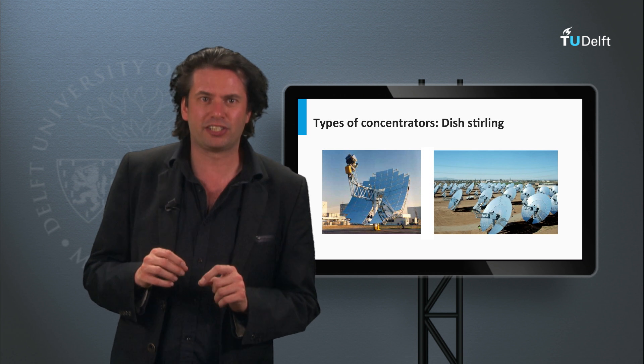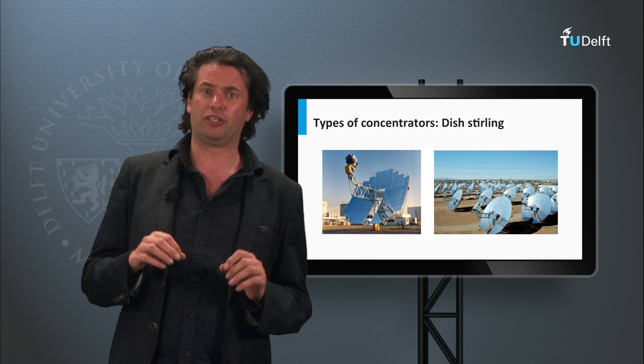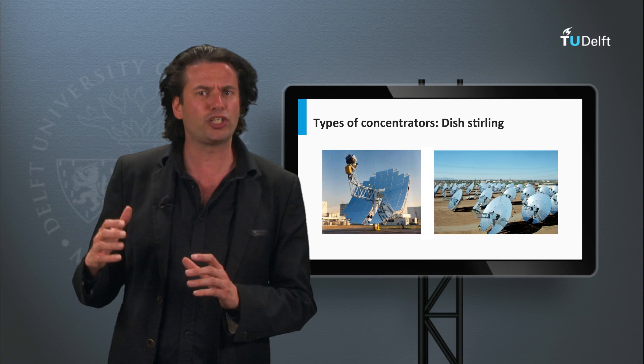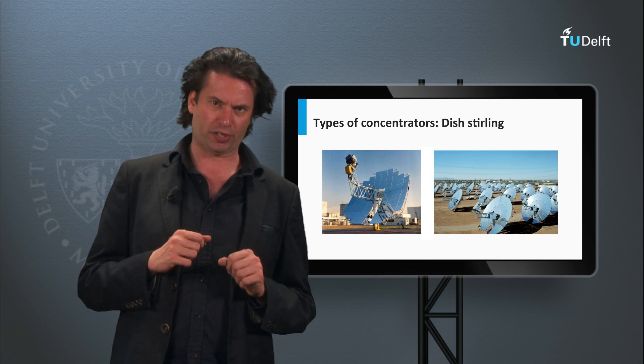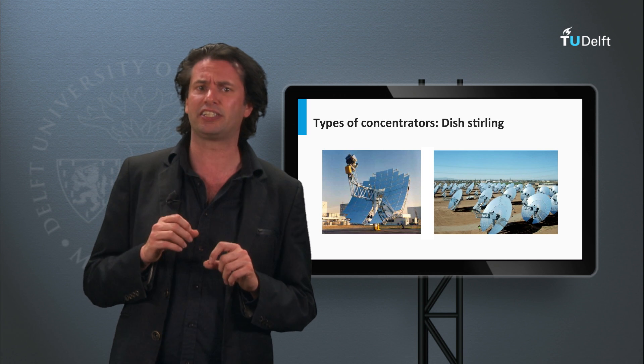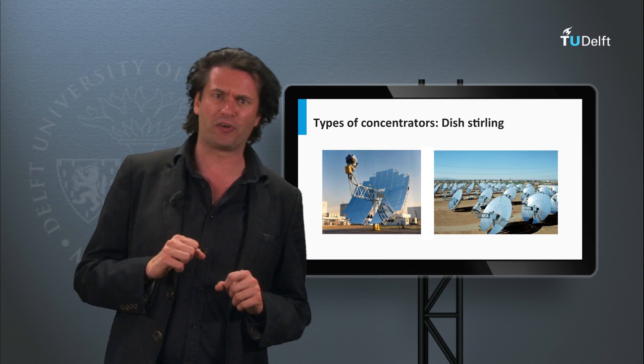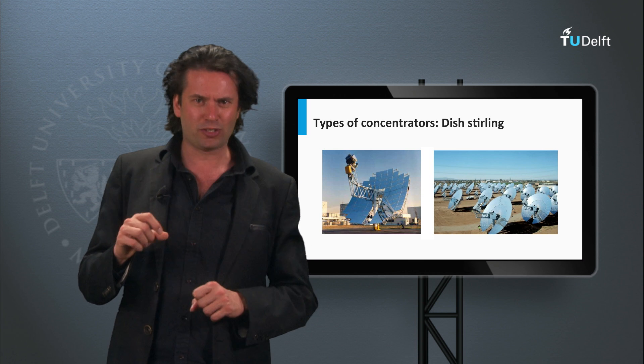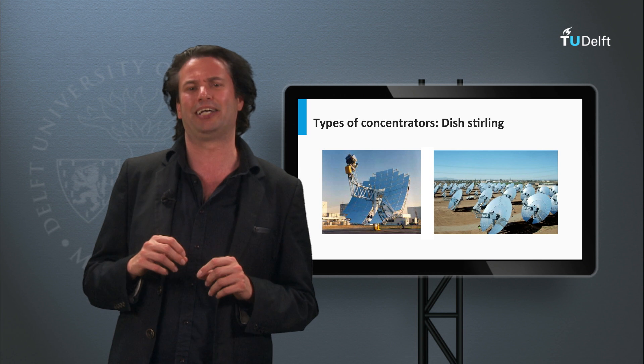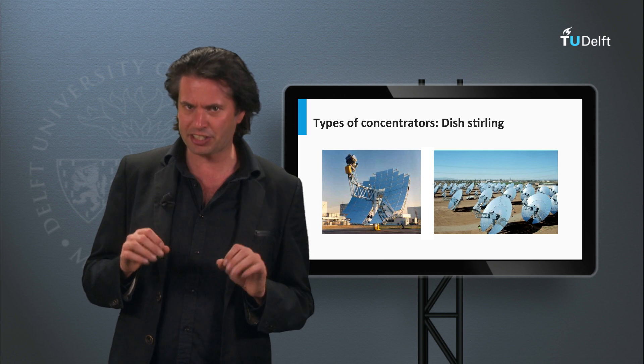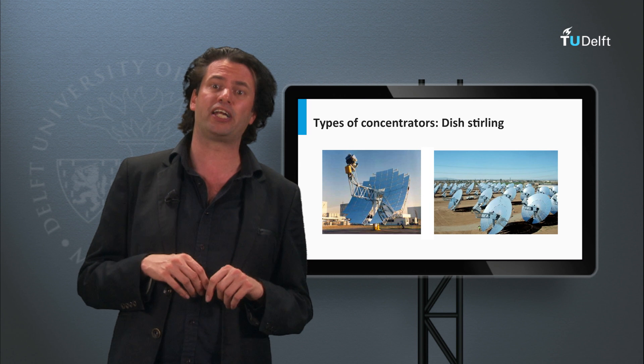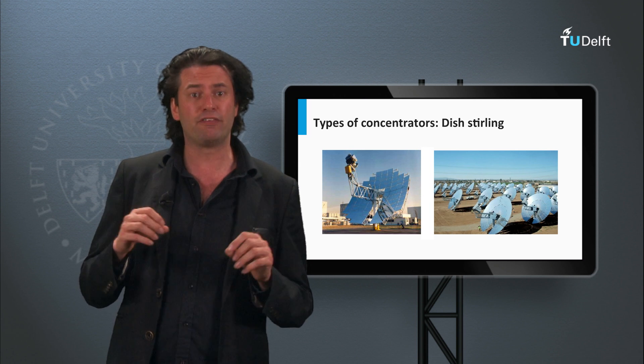Another important concentrator system is the dish-Stirling. A dish-Stirling or dish-engine system consists of a parabolic reflector that concentrates light to the reflector's focal point, where the working fluid absorbs the energy, heating up to 500 degrees Celsius and is able to operate a heat engine. These systems provide an overall efficiency of 31 percent, which is rather high. Several projects have been developed using this technology, such as the Big Dish in Canberra, Australia, or the NSTTF in Phoenix.